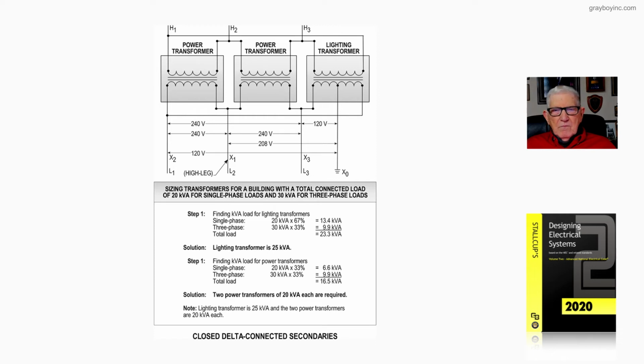Step 1, single phase load, 20 kVA times 67%, 13.4. Now, not being too simple, the 67% comes from taking 2 and dividing it by 3, because that's a 2/3 load there of that single phase. The 3-phase load then, 30 kVA times 33%, gives you 9.9. And again, not being too simple, 1 divided by 3 gives you 33%. Add the values together, you come up with 23.3 kVA.